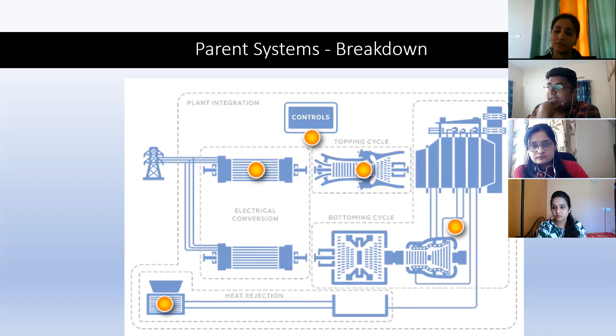So the distributed control system is kind of a local control system for each parent system, and then we have a control system for a simple cycle system. In a simple cycle plant, where it's just one gas turbine generating power, we use only one control system, and we typically don't call it a DCS. It's just a single point control system which we operate from a control room.